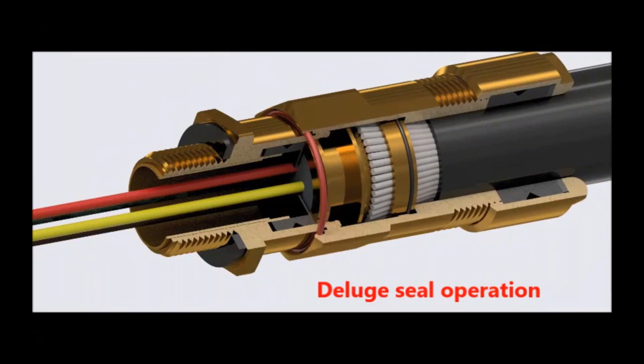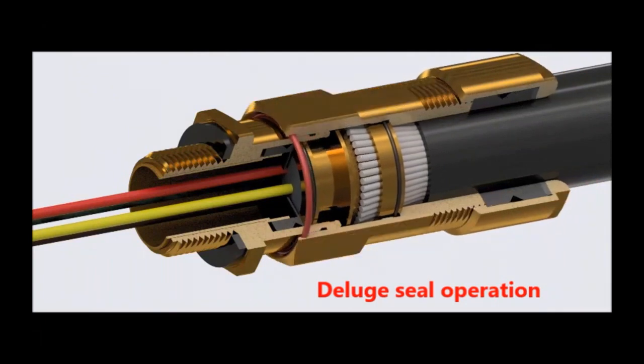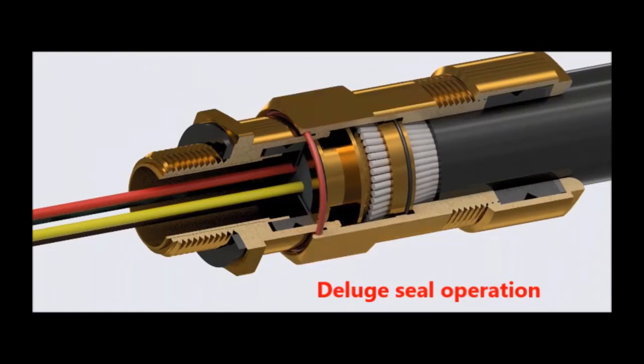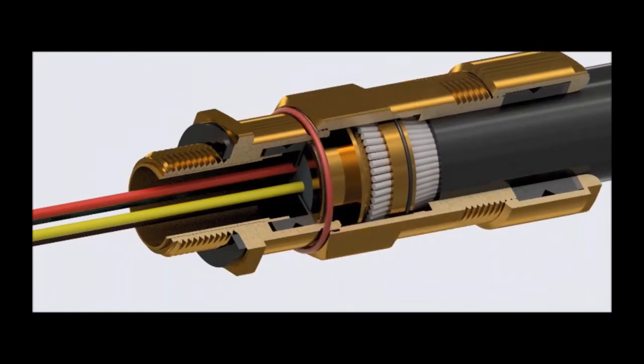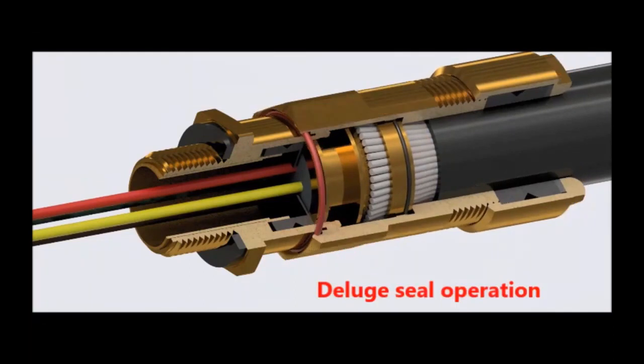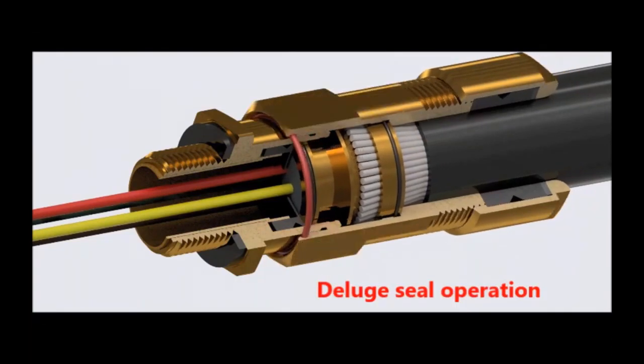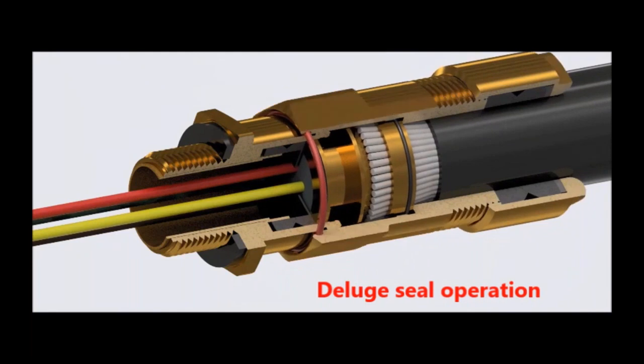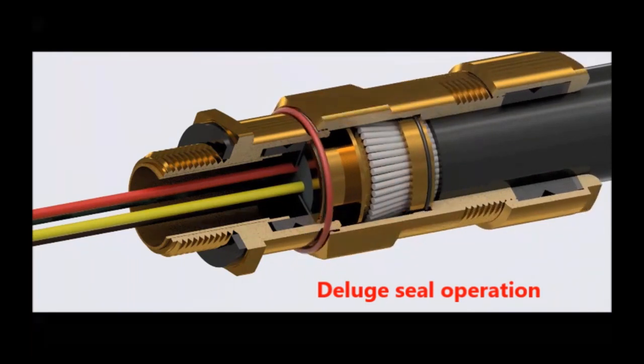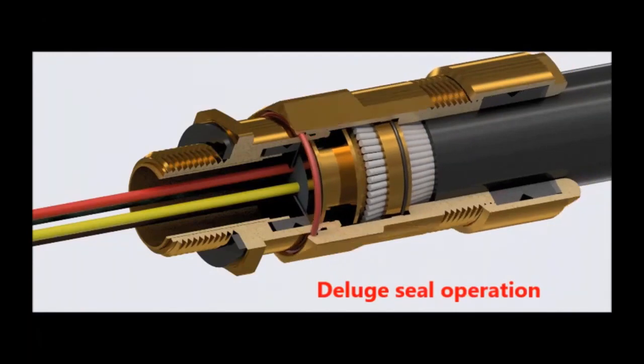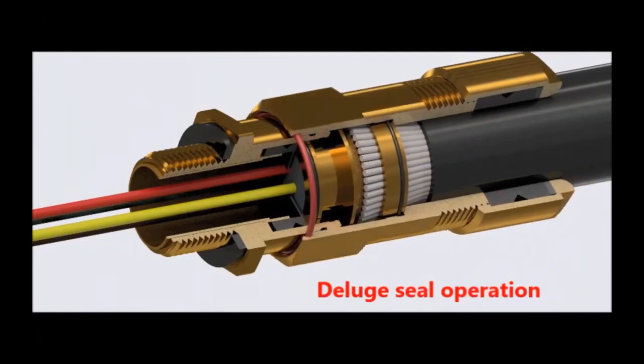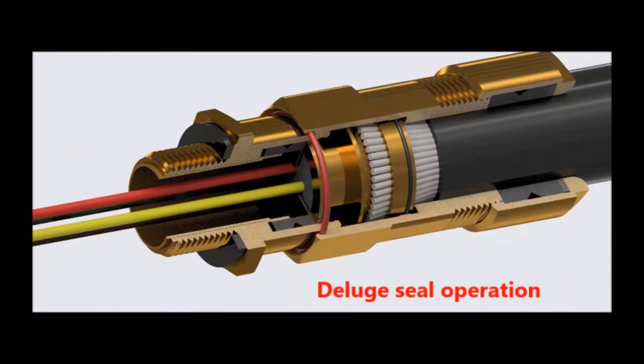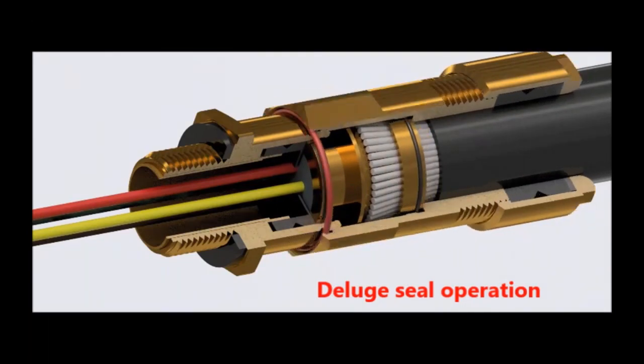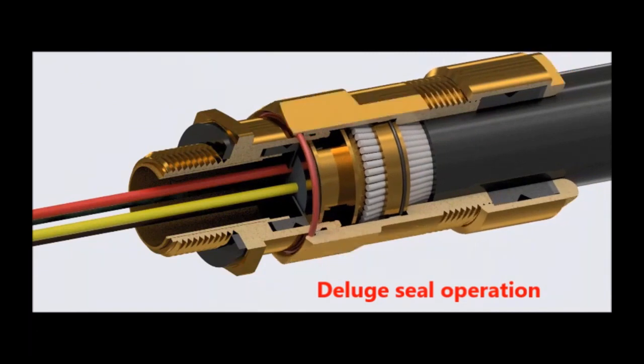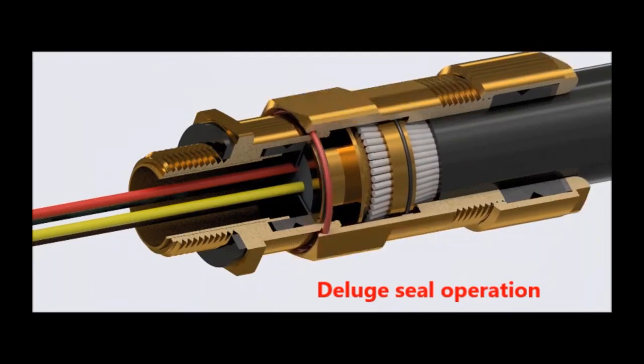So what can be done? Well, there's deluge seals. On this one, they have 3. 1, 2, 3. There's 2 inner seals, and then that one right there. So it's a clever design. You don't need to do anything. You don't have to pull a deluge seal. It's simplistic. It's removed the chance for human error. Instead of the manufacturer saying, well, it's the installer's responsibility, through hierarchy of control, yeah, instead of there being an administrative level of technique of you must do this, it's an engineered solution. You don't have to do anything.